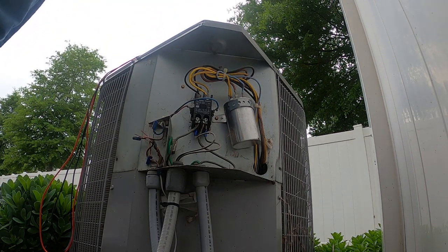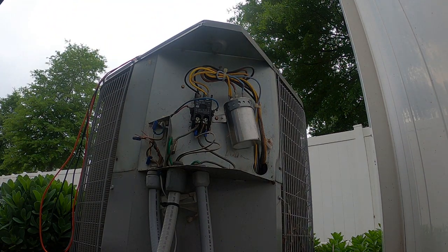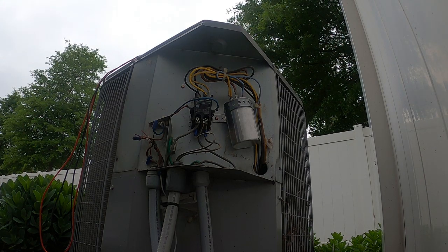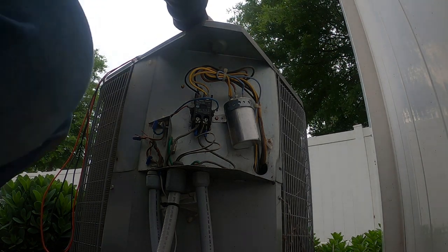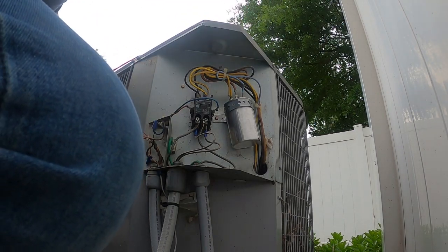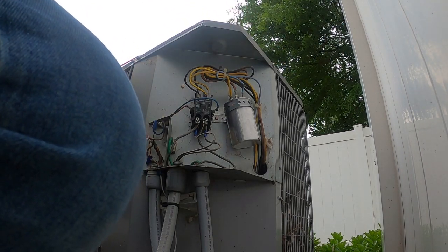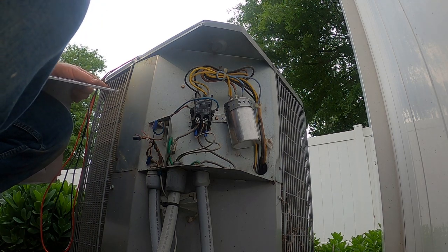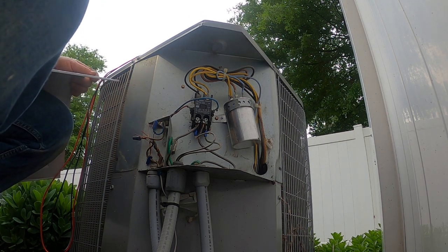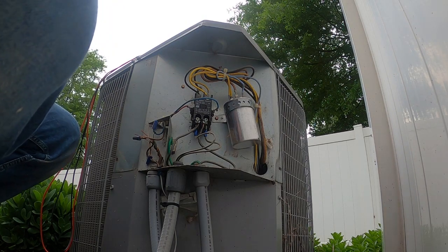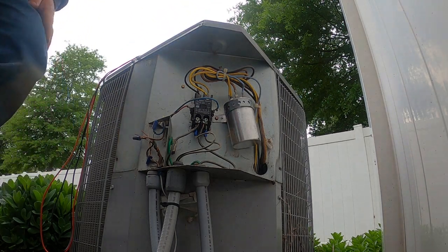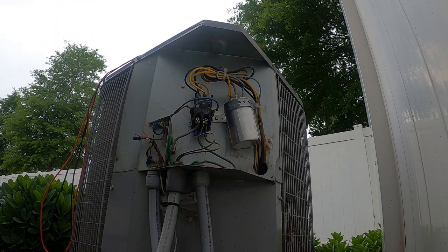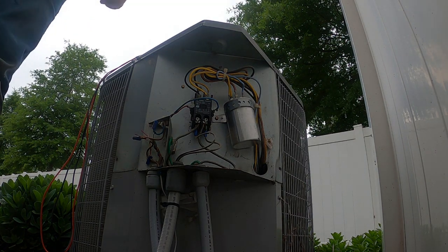So we're going to check it from out here. And of course none of these breakers are labeled, so what am I looking for on my sticker? What's my MCA? My MCA on this is 25 amps. So do I have a 25 amp breaker back here? Yes I do, right on the bottom.